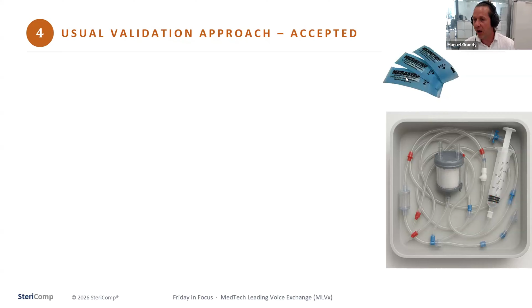Then also here you want to investigate, this is a volume inside of this tubing. Here you would also like to know, well, how much lethal conditions, how much kill do I have? And then the third BI you would maybe put here, okay? This is the so-called longest gas pathway. You close here, you can do this, and then you make sure that the EO goes through the whole set to this point here. So this is a high challenge. You could also remove it and place the BI here in the middle with a T or something. But this is also something that is done a lot if you can afford it, to challenge the process a bit, okay?